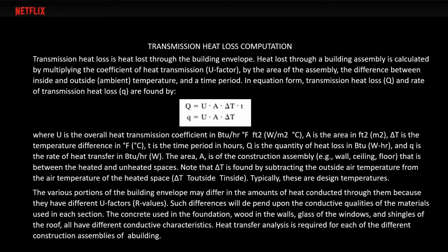where U is the overall heat transmission coefficient in BTU per hour Fahrenheit, ft2 or W over m2 Celsius. A is the area in ft2 or m2. Delta T is the temperature difference in Fahrenheit or Celsius. T is the time period in hours. Q is the quantity of heat loss in BTU or W-hr. And small q is the rate of heat transfer in BTU per hour or W.